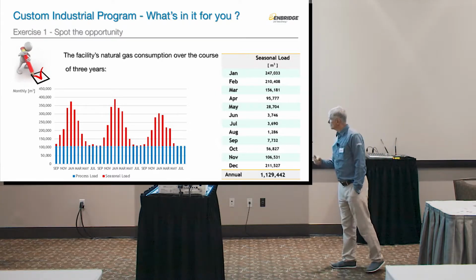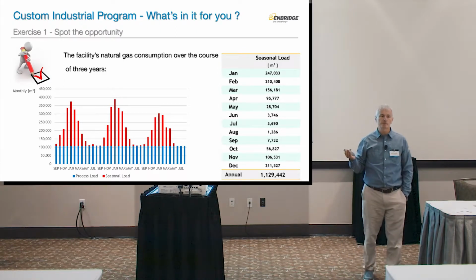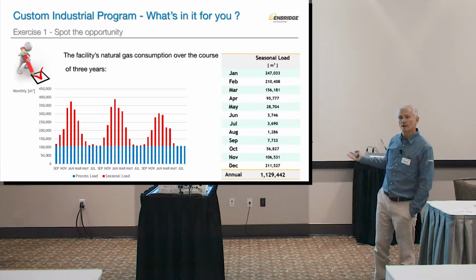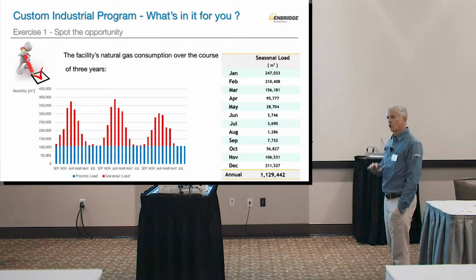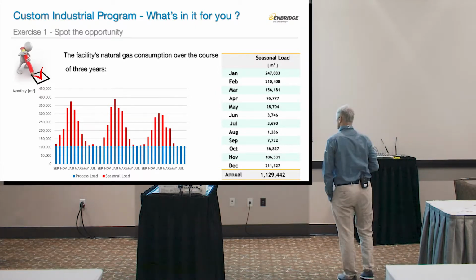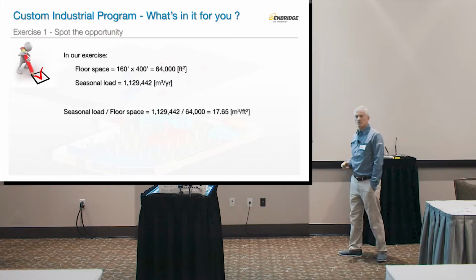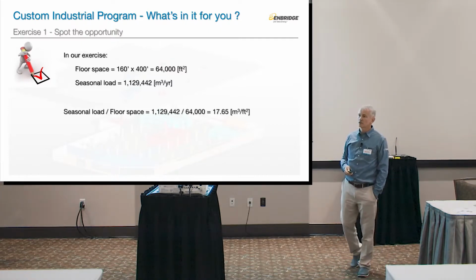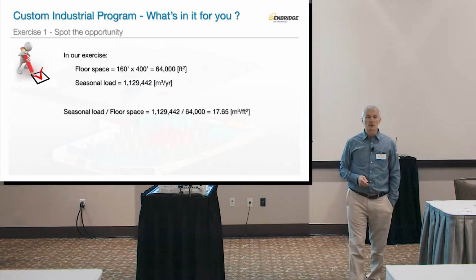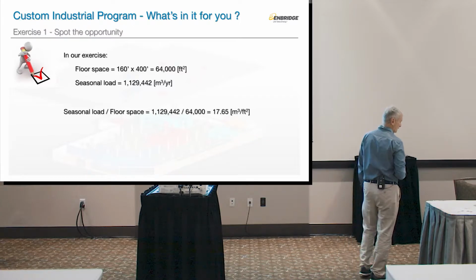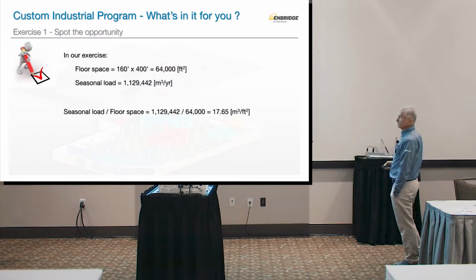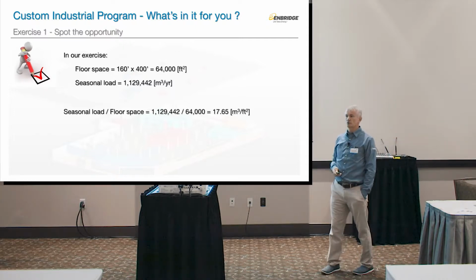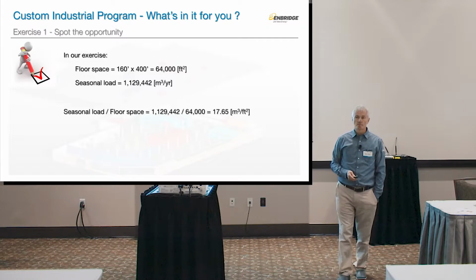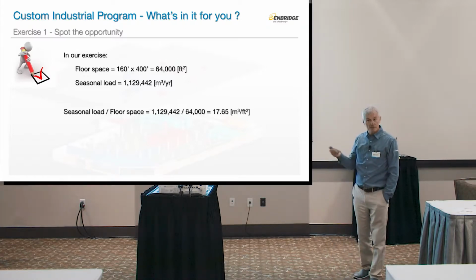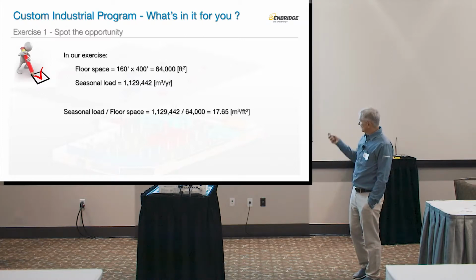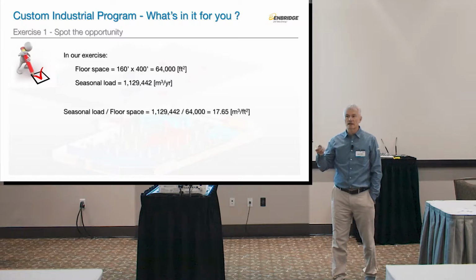So the graph can tell us a lot of things, right? We didn't do much work. We just plotted our consumption, and it already raised 3 or 4 questions, all valid questions. The other one that I would also like you to think about is, we're talking 64,000 square feet of space, and it takes us 1.1 million cubic meters to heat it. If you divide those two, it means 17 cubic meters for every square foot of space. That is an enormous number. It might be something that is really necessary, but if I see a number like that, I automatically go, let's analyze where this energy is going.